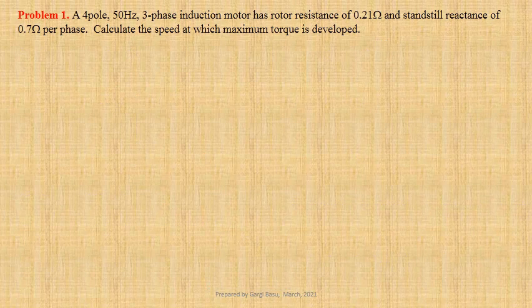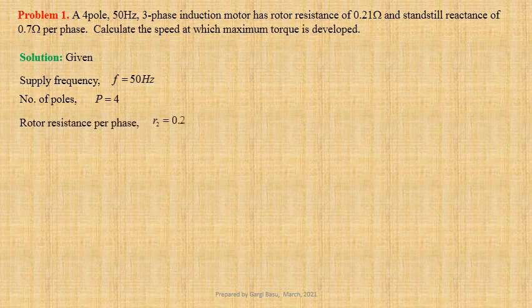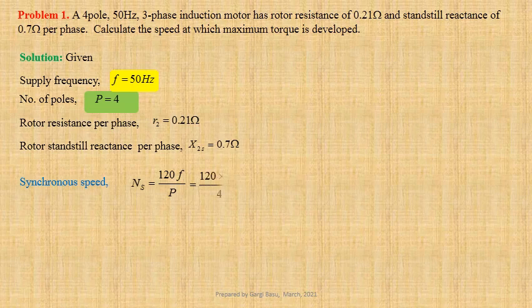Problem number 1. A 4-pole, 50 hertz, 3-phase induction motor has rotor resistance of 0.21 ohm and standstill reactance of 0.7 ohm per phase. We have to determine the speed at which maximum torque is developed. Given data: supply frequency F equals 50 hertz, number of poles P equals 4, rotor resistance per phase R2 equals 0.21 ohm, rotor standstill reactance per phase X2S equals 0.7 ohm. Synchronous speed Ns equals 120F by P equals 120 into 50 divided by 4 equals 1500 RPM.